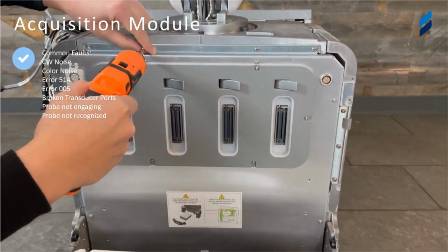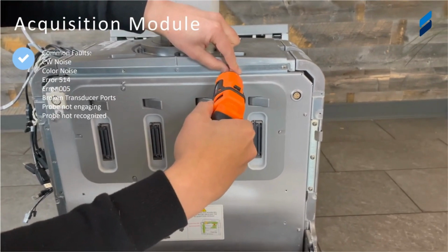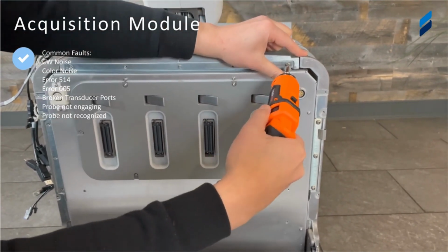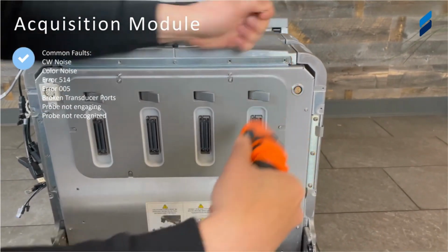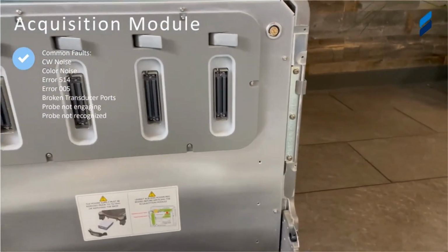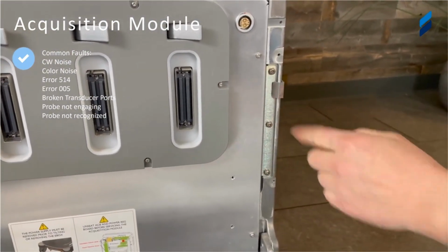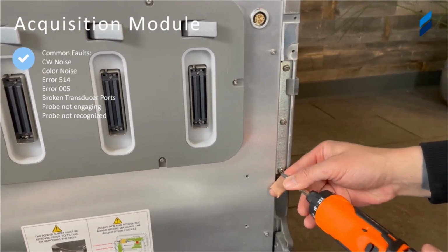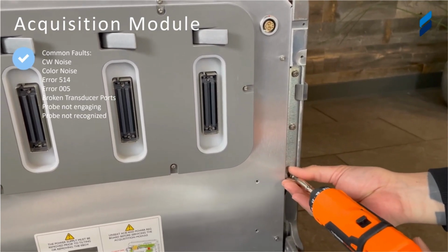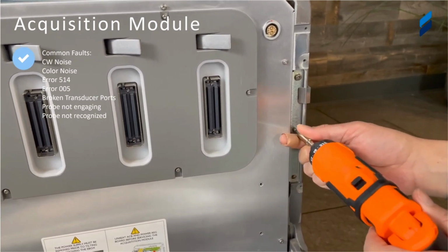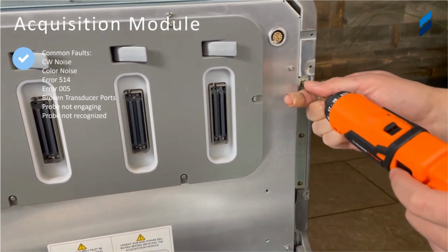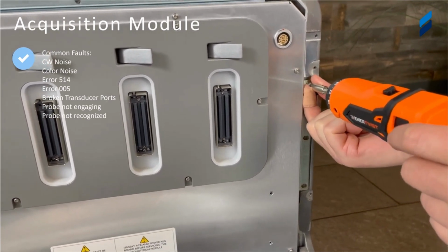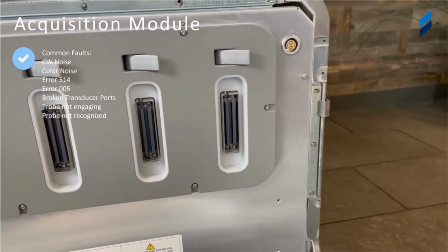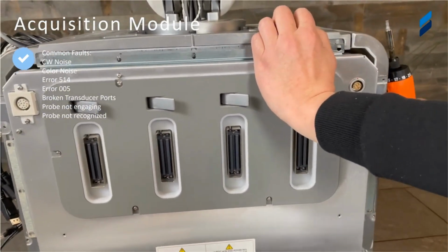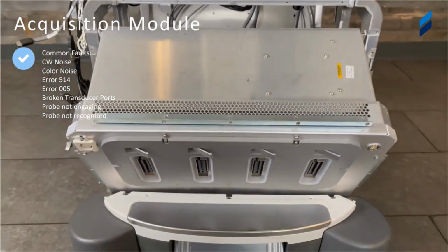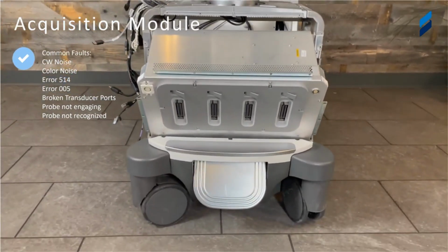You're going to see this process a few times in this training. We're moving at real-time speed here, and we just wanted you to see it a few times so you're comfortable with the process. And there's that right latch that will prevent the whole e-box and acquisition module assembly from tilting forward. It's going to tilt forward with all the screws removed. That's what's going to hold it up, so there's no accidental tilting and unnecessary impact to the assembly. So now that we have all the screws removed, we're going to pull out to the right on that tab and let it fall forward.